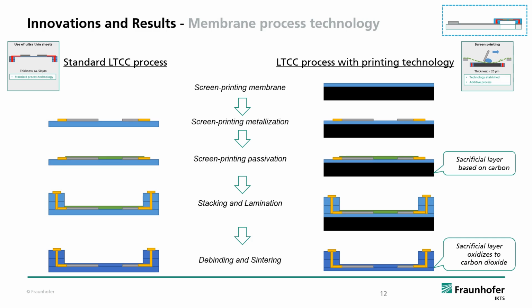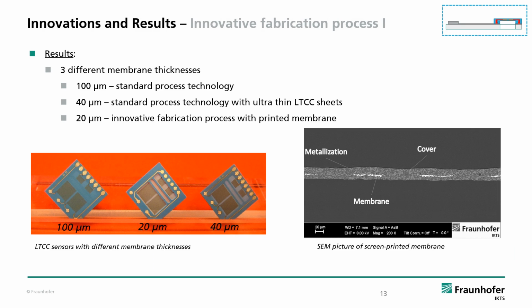So on this slide I want to compare the results of the innovative fabrication process 1 with the standard technology. We prepared sensors with different membrane thicknesses. One has a 100 micron thick membrane prepared with the standard LTCC process, analog to the standard process with the ultra-thin LTCC sheets, which results in a 40 micron membrane. The new technology with screen printing, instead of using LTCC green sheets, results in a 20 micron membrane.